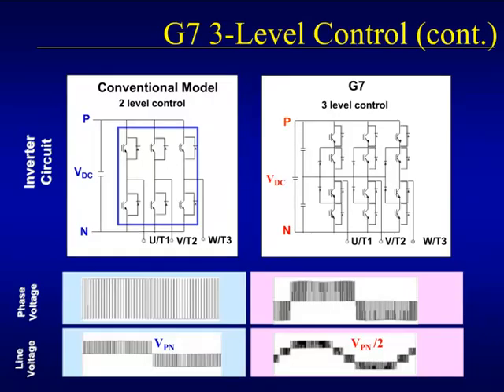The term 3-level control derives from the fact that each of the drive's output phases has 3 different voltage levels that it can source: 0 volts, half the bus voltage, and the full bus voltage level. A standard 2-level control can only source full bus voltage or no bus voltage. The capability to source a third voltage level comes from the use of 6 extra output transistors and 2 more bus capacitors. The extra hardware is utilized to create a midpoint that is used to source only half the bus voltage when only that voltage is necessary to create the appropriate output voltage waveform.